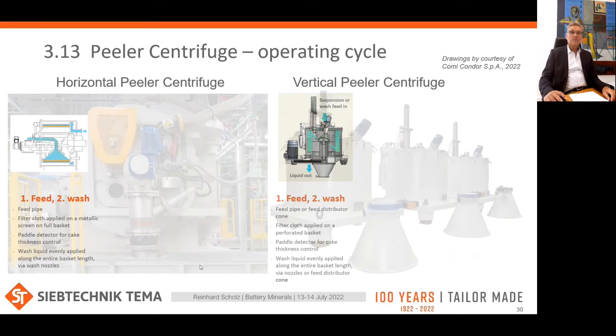In a vertical peeler, the suspension enters via this feed vertically, in the horizontal peeler horizontally. Under the influence of centrifugal force, liquid filters through the filter cloths and through the holes of the baskets. Even fine solid particles are retained by the filter cloths, unlike in the pusher. Cake thickness is controlled by a mechanical feeler detector. It stops the loading phase once the desired cake thickness is reached. For washing, there's no difference between the two types. The washing liquid is dispensed over the solid product along the entire length of the basket. The wash liquid passes through the product and then further through the filter cloth and the holes of the basket. It replaces retained mother liquor in the cake with pure wash liquid.